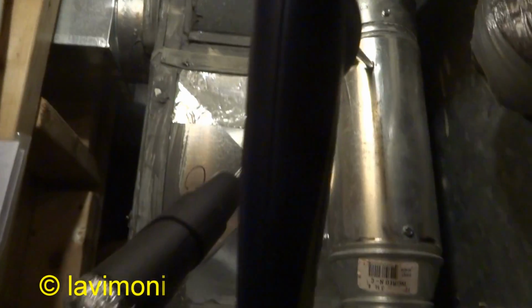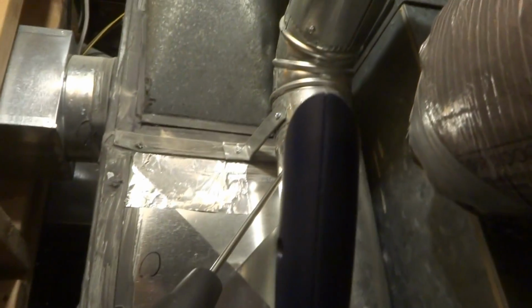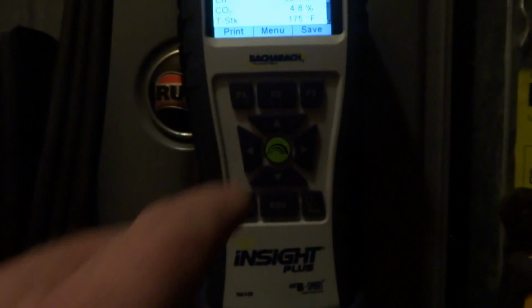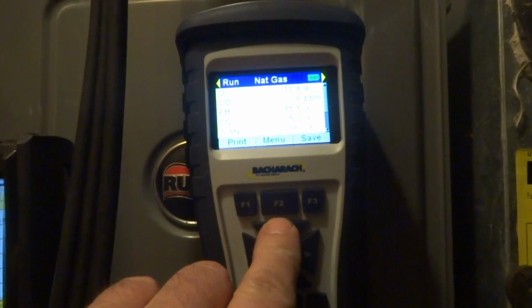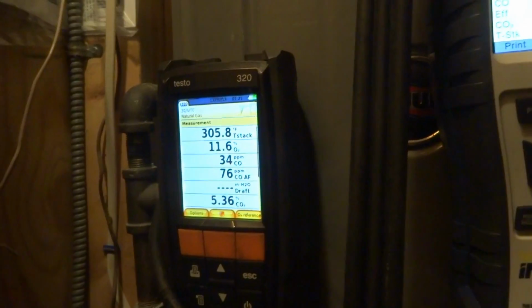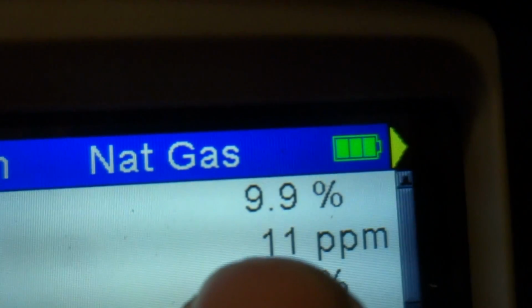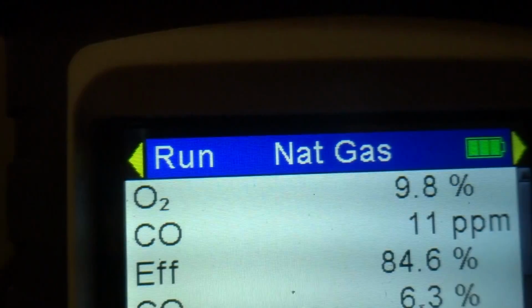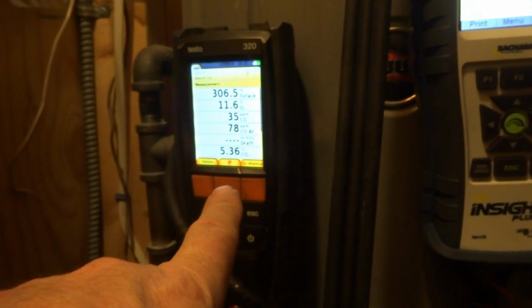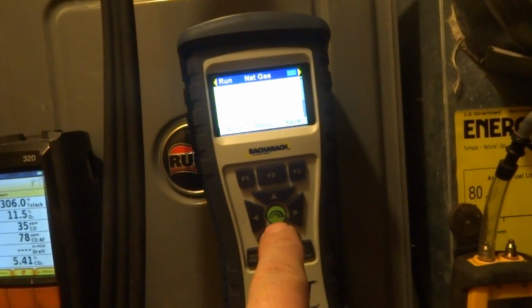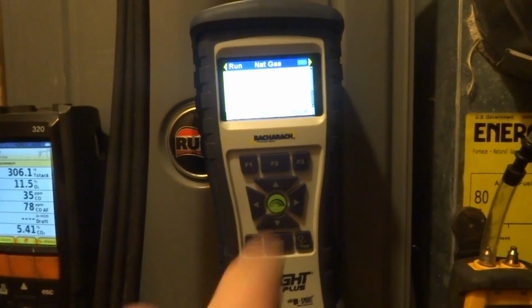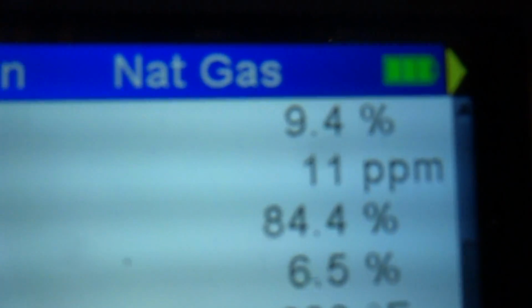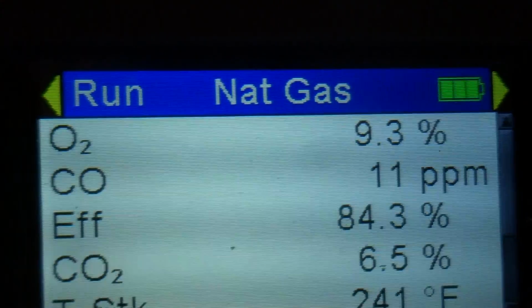Bacharach's got a much thicker probe - you see the difference, the angle with the probe is so much bigger. See the CO2, how low it is compared to the other ones. That one's got a brand new CO sensor. This one's got a brand new CO sensor and an oxygen sensor. I always felt that the ppms on this thing was really low on the CO.